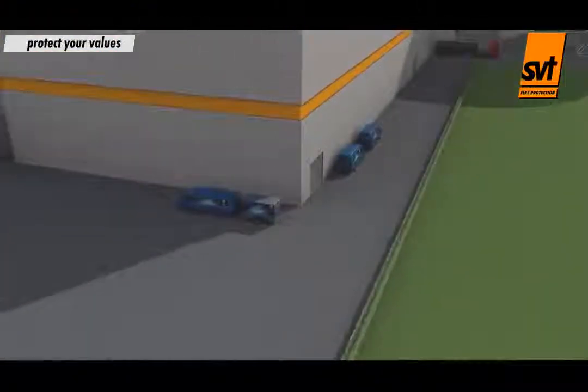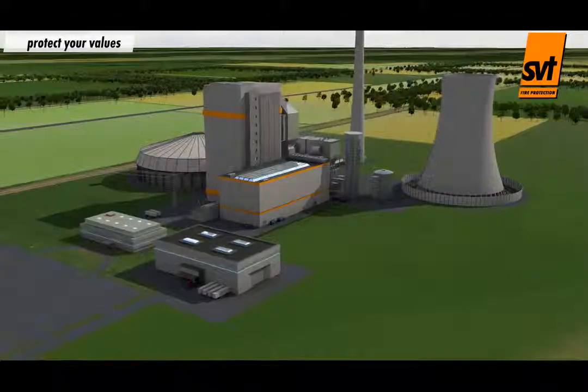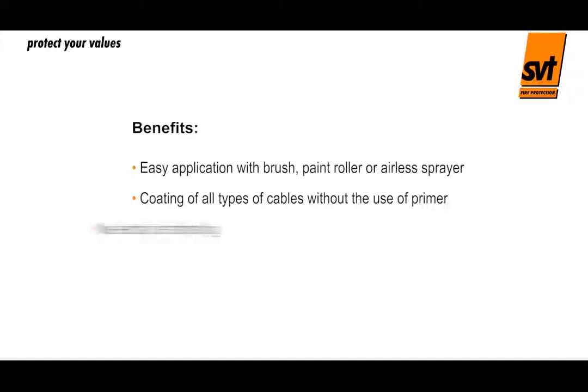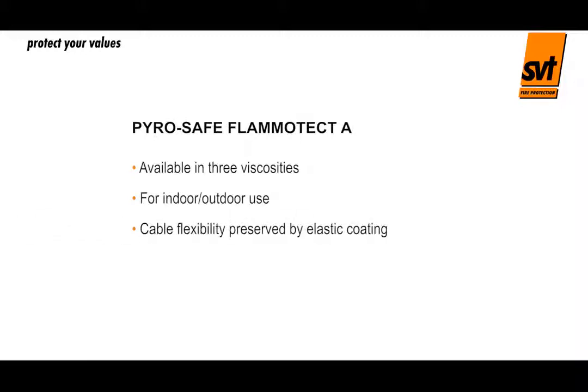SVT's PyroSafe Flammotect A cable coatings for indoor and outdoor use, or PyroSafe Flammoplast KS1 for indoors, provide effective and cost-efficient fire protection. Benefits include: easy application using a brush, paint roller or airless sprayer; coating of all types of cables without the use of primer; no electrical de-rating; cost-efficient application; and solvent and halogen free formulation. PyroSafe Flammotect A is available in three viscosities, for indoor and outdoor use, with cable flexibility preserved by its elastic coating and resistance to many chemicals.